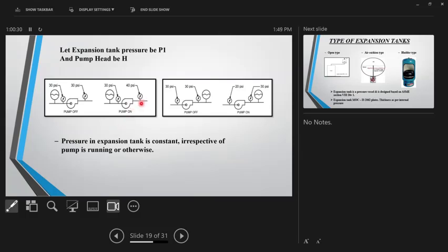Now here it will be 40. After some time, it will be 39. There'll be some drop. Here it will always be constant. Whether the pump is running or not running, the expansion tank is at the bottom, after the pump, in between floors, terrace, basement, it doesn't matter. If the temperature is not changing, the expansion tank pressure will always be constant. That is why it is also known as a reference pressure as per AECOM.